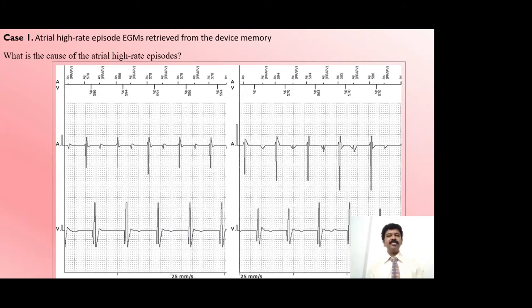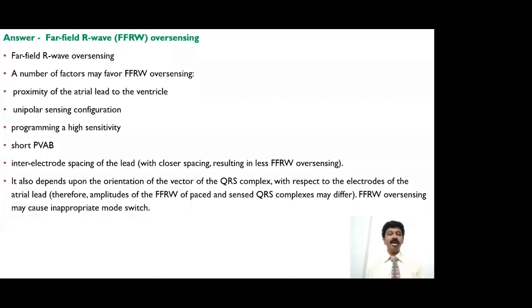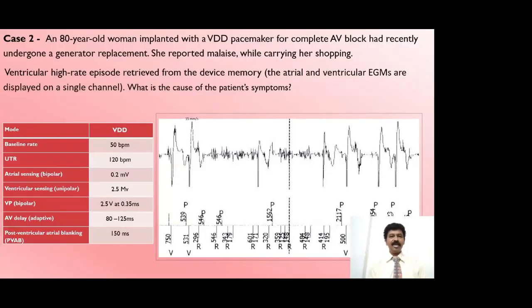That means it could possibly be far field R wave sensing. Especially this will happen when you program the leads to unipolar sensing, and if the leads are very close, like atrial appendage and outflow tract leads, and especially if you have set your sensitivity thresholds very high. So this far field R wave sensing can be avoided by programming sensitivity to a lower level and configuring the leads to bipolar sensing.